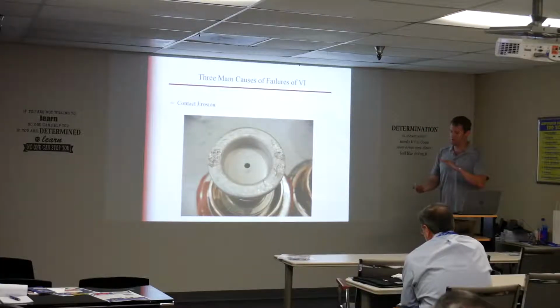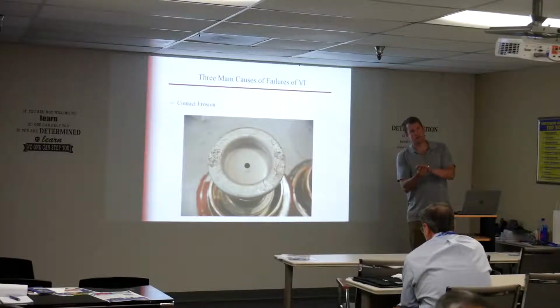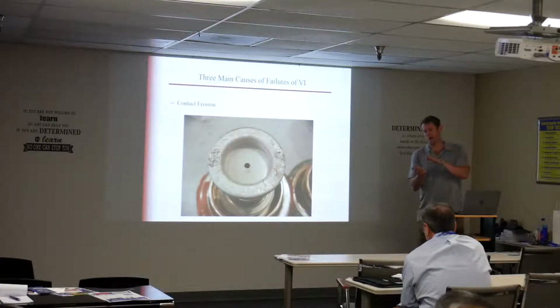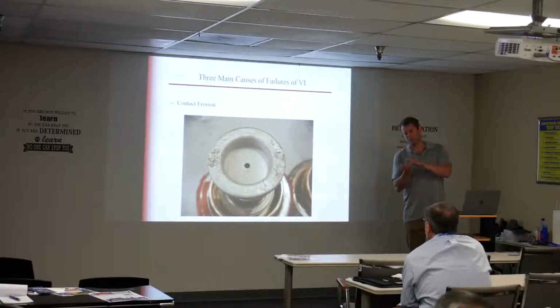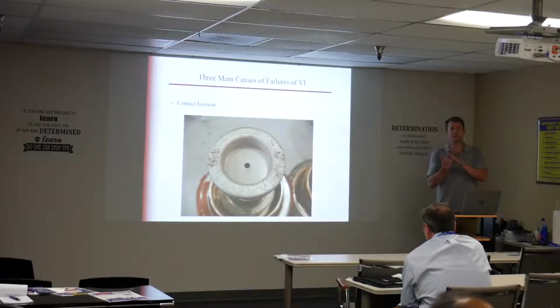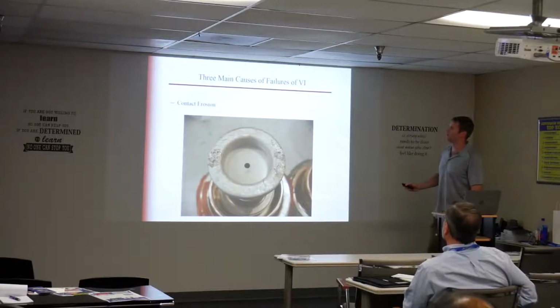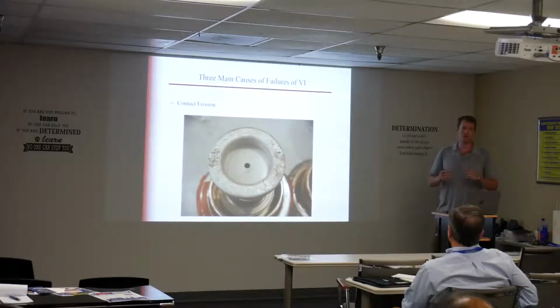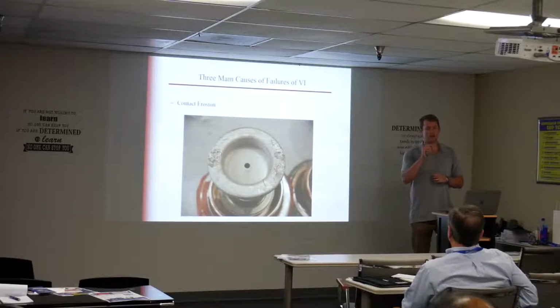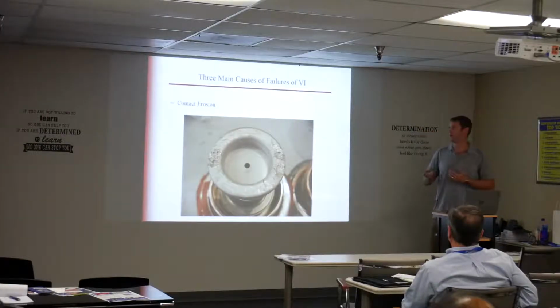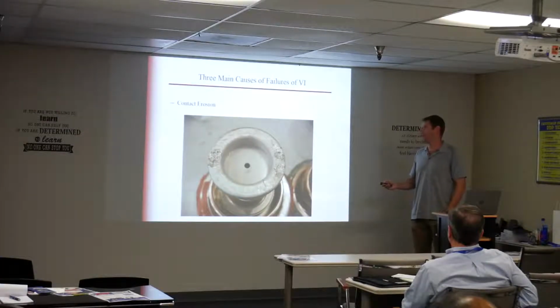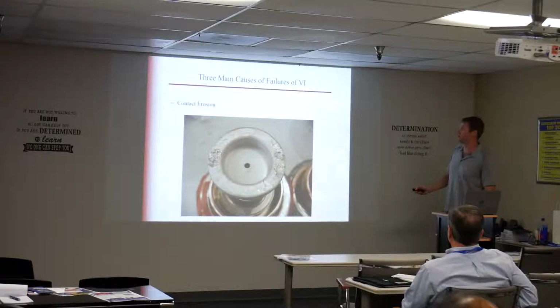So these breakers have a wipe spring holding the contacts closed, but eventually, like I said, if the bottle wears, it gets too short, that wipe spring can't maintain enough pressure and the contacts will pop open. This is mostly a visual measurement. Each breaker manual will have a contact erosion indicator or a dot on the movable end. Once that dot's gone up in the bottle, there's some way to measure this. You'd also check contact resistance. You start getting high contact resistance measurements, or they start to get off, you'd find this.